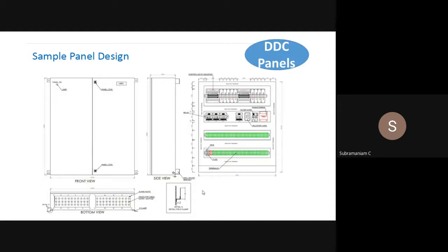So this is the DDC enclosure box which I talked about. Your DDC controllers are going to come inside. There will be a transformer which will give 24 volt AC/DC power supply, and all the terminations, all your NO/NC contact relays and so on will be mounted here for binary output. So if you want to become a BMS engineer and expand, you should know good electrical wiring. Electrical is a very important thing which we should know, and people can start manufacturing these panels. It's a good field where entrepreneurs can do a lot of expansion of their business.